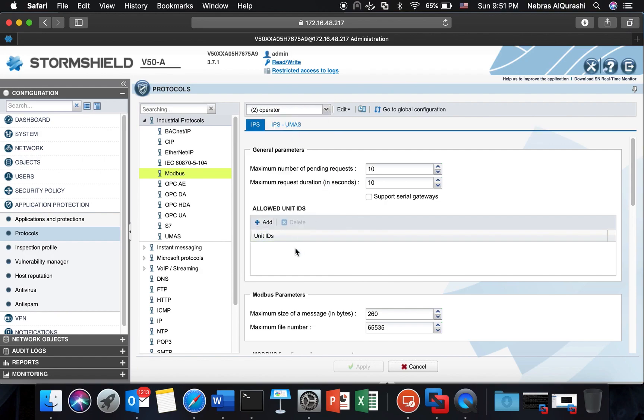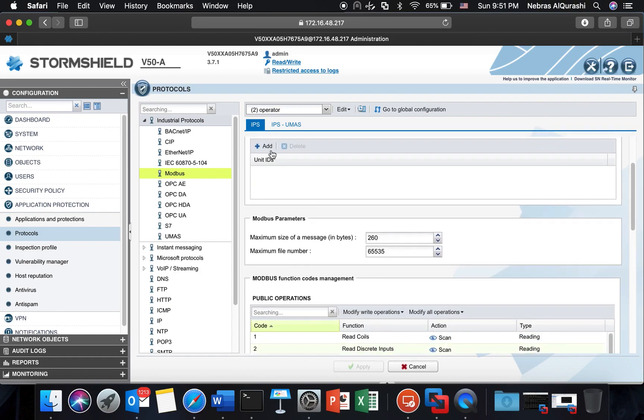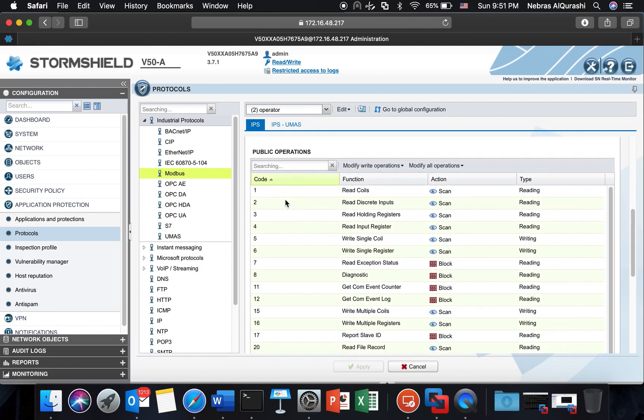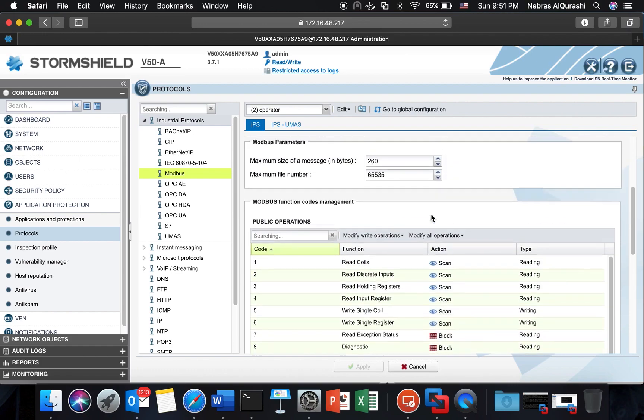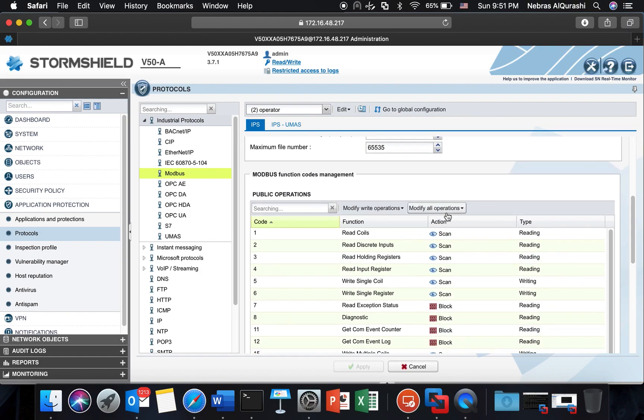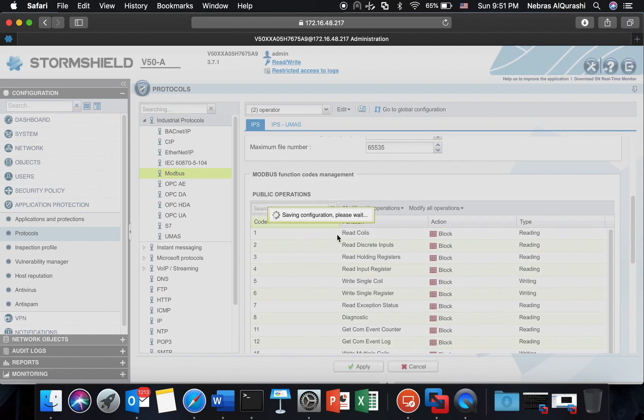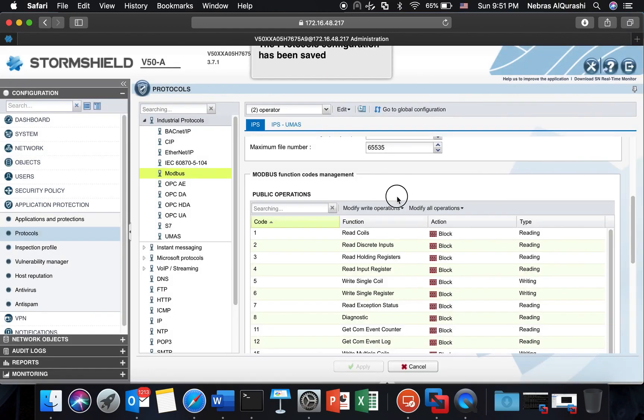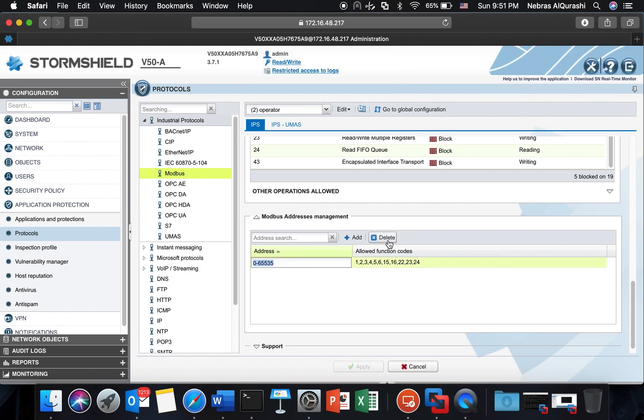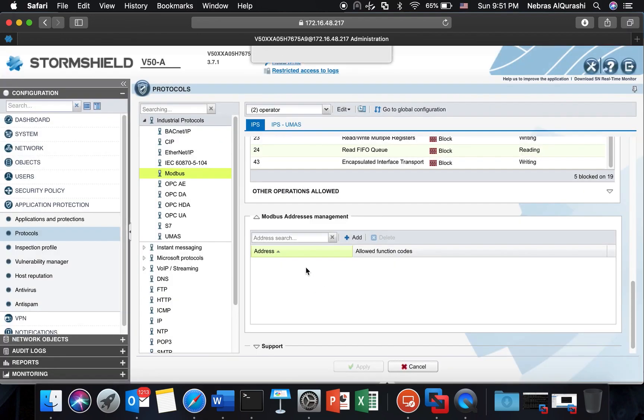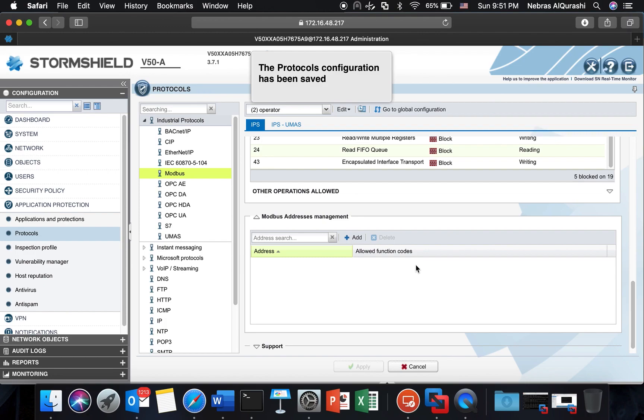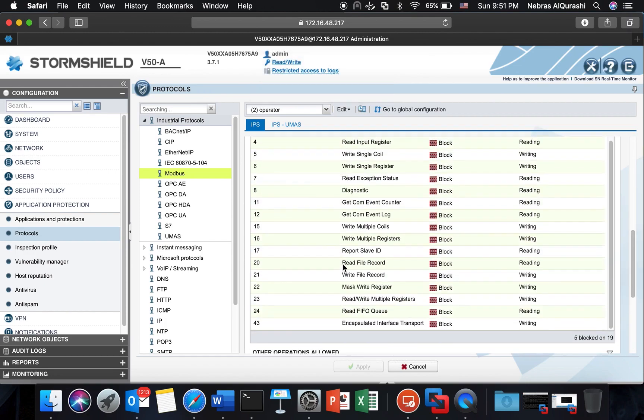I will not set a unit ID. I will keep it empty so this will cause an error because I need to define one and also I want to set all the Modbus function codes. I want to set them all to block because I need to identify. And then at the Modbus address management I will remove this. I don't want to have anything matching with any address with any function code. So this is the first stage, this is what I do to prepare.